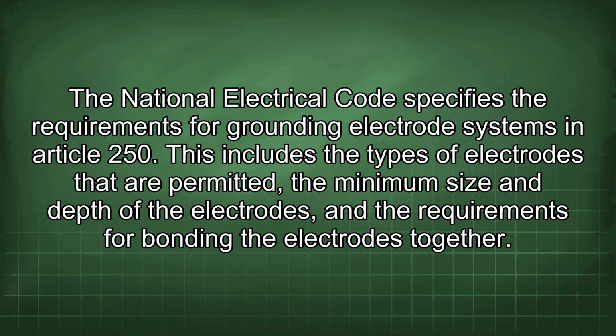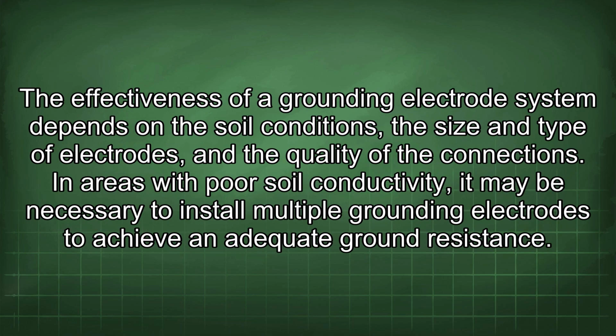The National Electrical Code specifies the requirements for grounding electrode systems in Article 250. This includes the types of electrodes that are permitted, the minimum size and depth of the electrodes, and the requirements for bonding the electrodes together. The effectiveness of a grounding electrode system depends on the soil conditions, the size and type of electrodes, and the quality of the connections. In areas with poor soil conductivity, it may be necessary to install multiple grounding electrodes to achieve an adequate ground resistance.